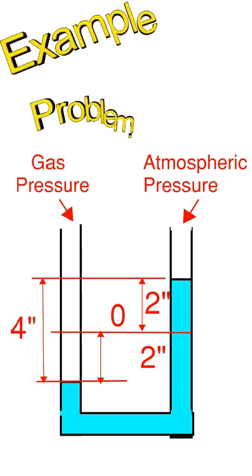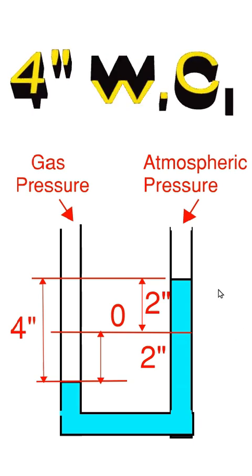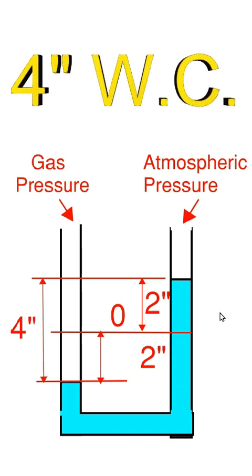In this example problem, the left side of the tube is connected to the gas pressure. The right side is open to the atmospheric pressure. If it went two inches up on the right side and two inches down on the left side, it accumulates the total height of four inches. So your water column is equivalent to four inches of water column.